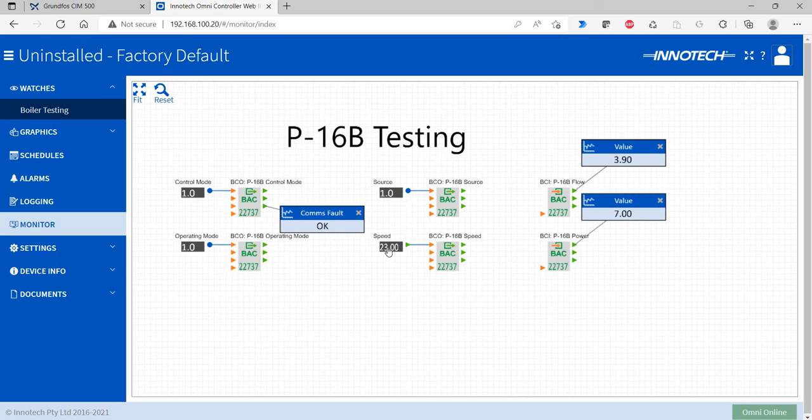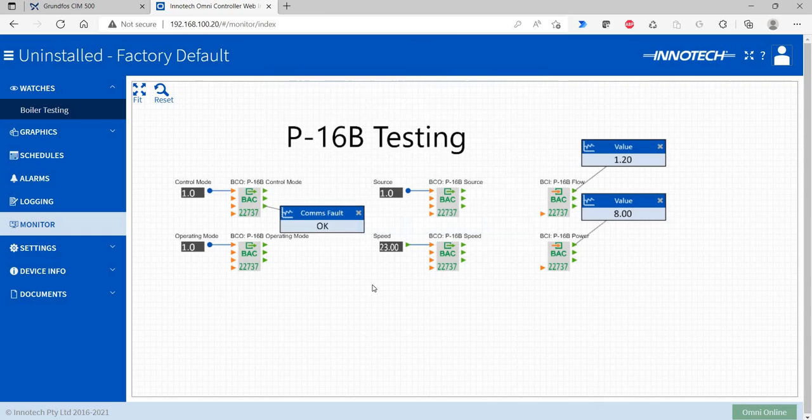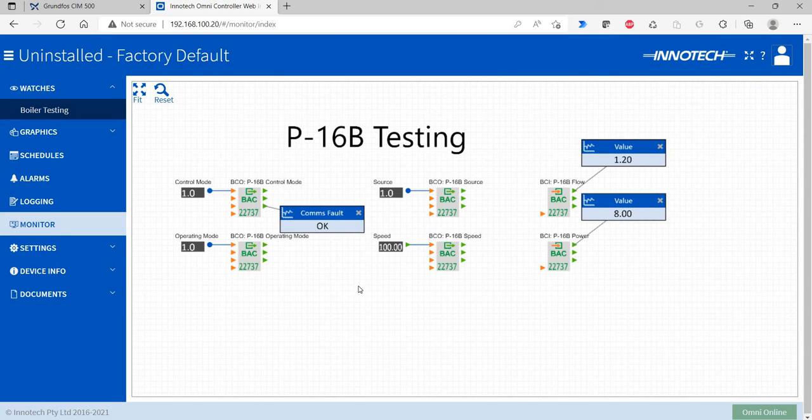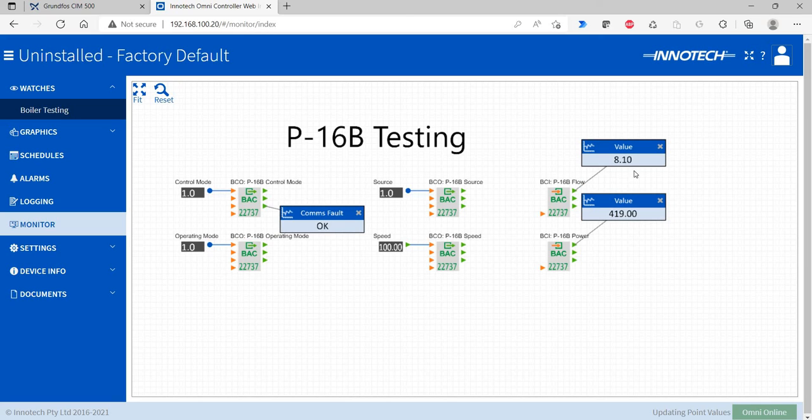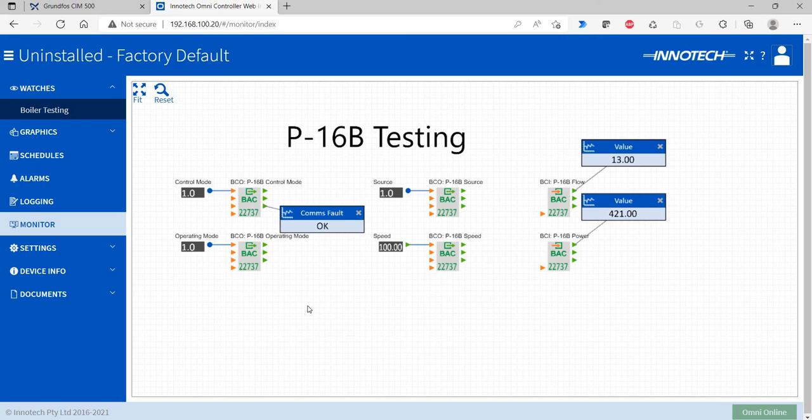Now it's running already from other settings we've given it before. Actually it's taking that speed setting right now, so if we wrap it up to 100, we should see about 420 watts consumed, which is actually pretty good for how much flow we're getting. This updates every 5 seconds for this testing. There we go. 419 and 8.1. Okay, there we go. Pretty good flow for how many watts we're burning.